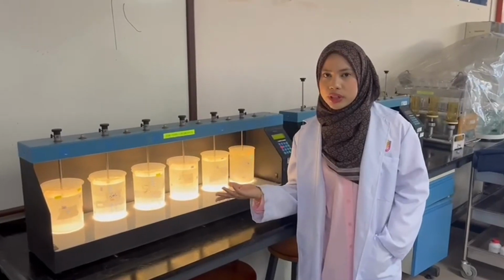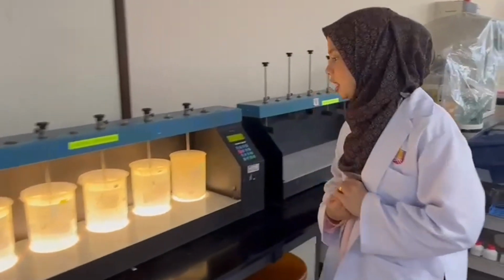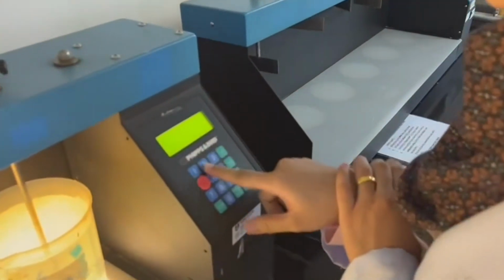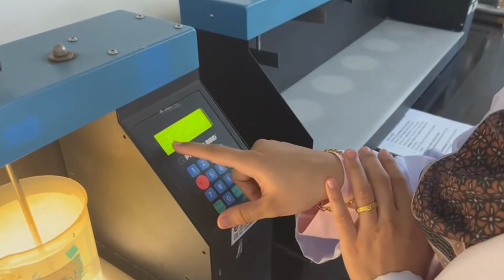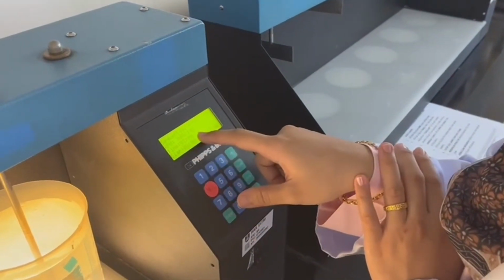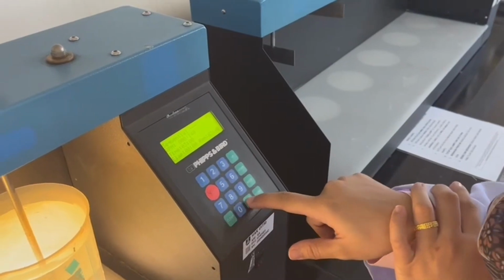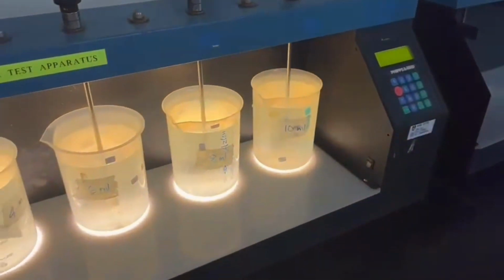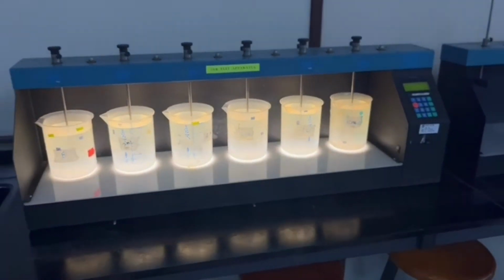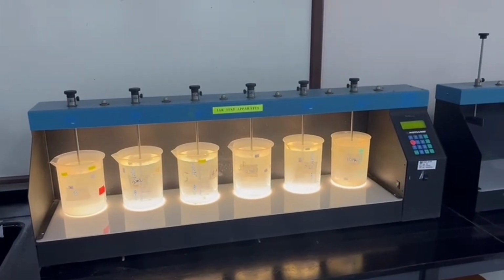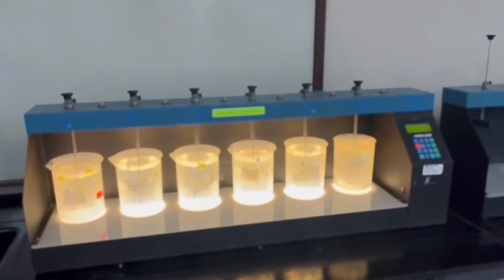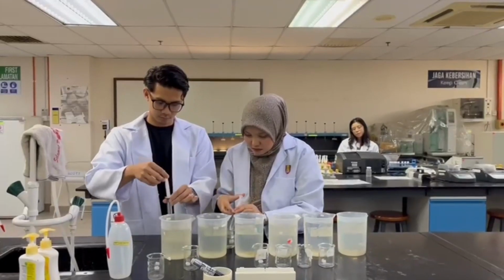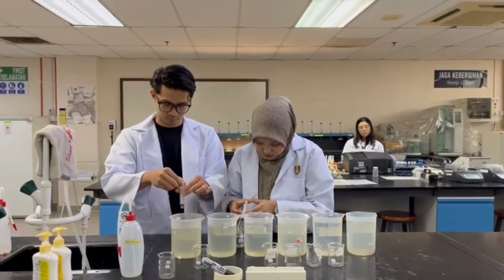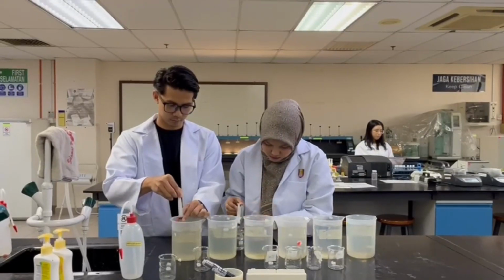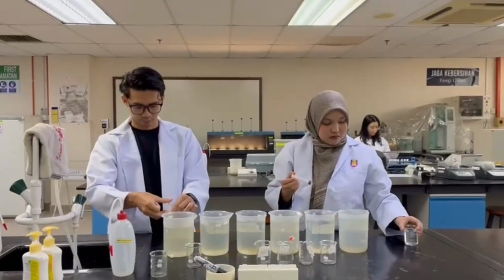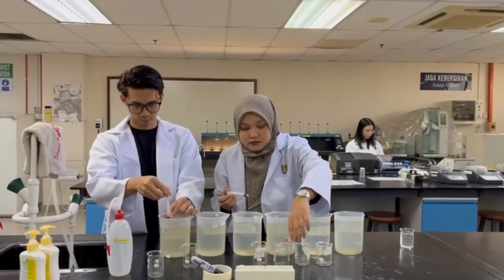To use the jar test machine, we have to put down the stirrer into the beaker, then press number 2 using 140 rpm for 3 minutes and then press start. After it's done, we have to wait for 15 minutes to let the sediment settle down. After the 15 minutes is over and the floc has settled at the bottom of the beaker, we use a syringe slowly to transfer the water sample into the small beakers.